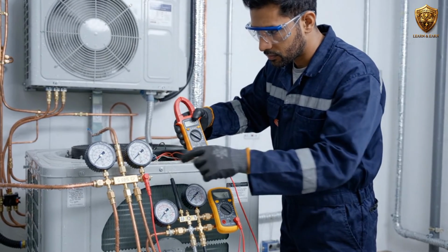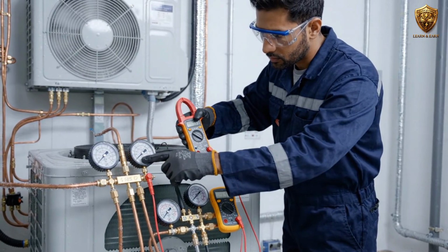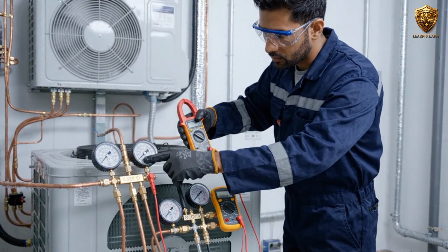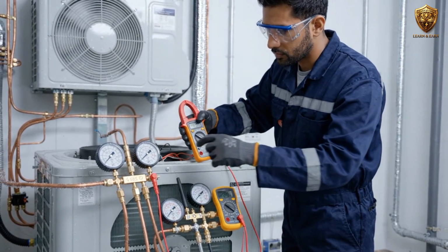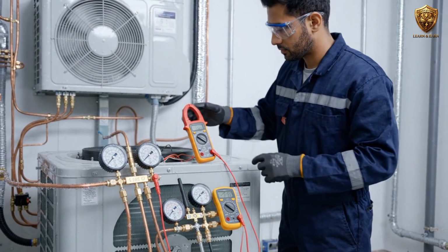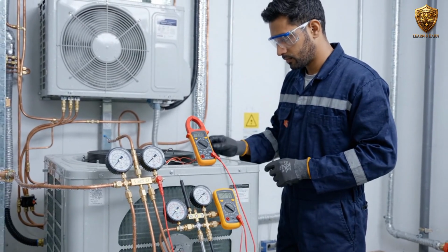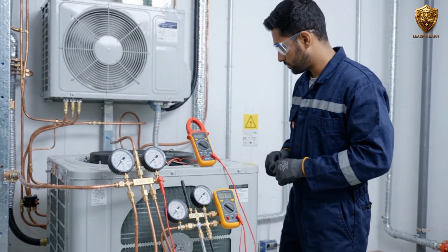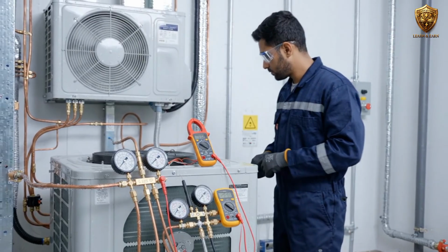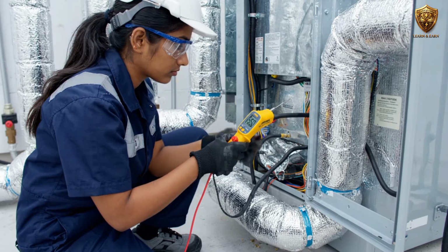When an AC is not cooling, think in a sequence: confirm the complaint, check the basic operating conditions, inspect airflow, verify electrical operation, evaluate condenser performance, and only then move deeper into refrigeration and compressor diagnosis. Use the system's symptoms to decide what to test next.